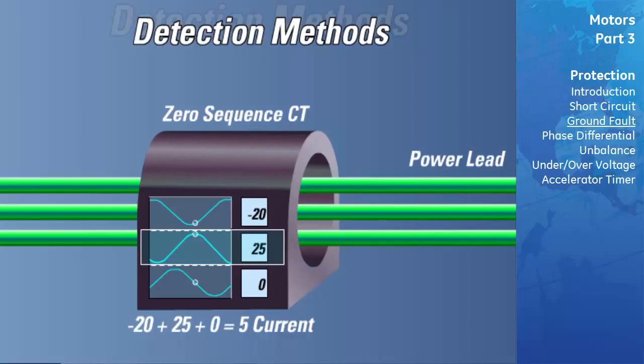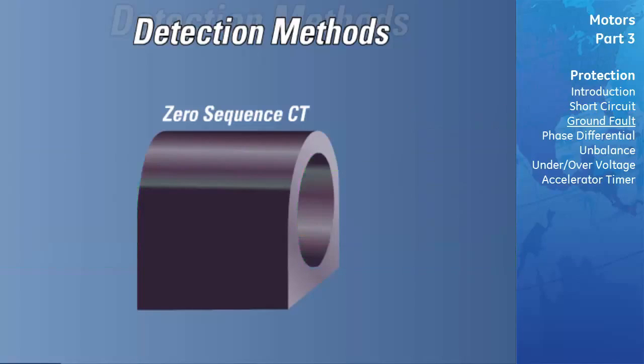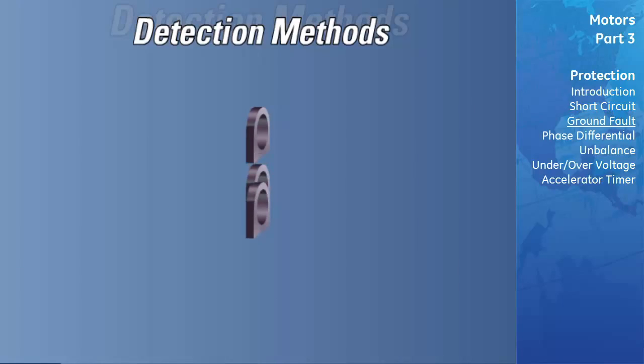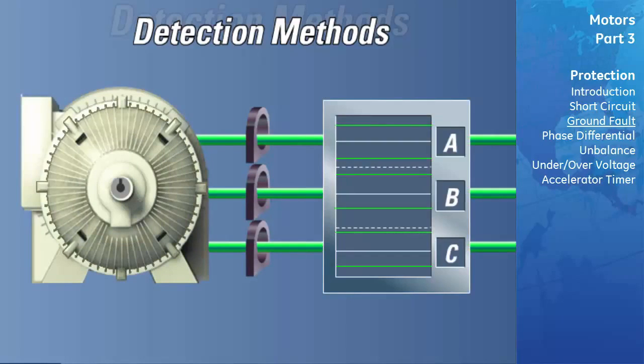The Residual Ground Fault Connection. If the cables are too large to fit through the zero-sequence CT's window, or the trench is too narrow to fit the zero-sequence CT, the residual ground fault configuration can be used. This configuration is inherently less sensitive than the zero-sequence configuration, owing to the fact that the phase CTs are not perfectly matched.